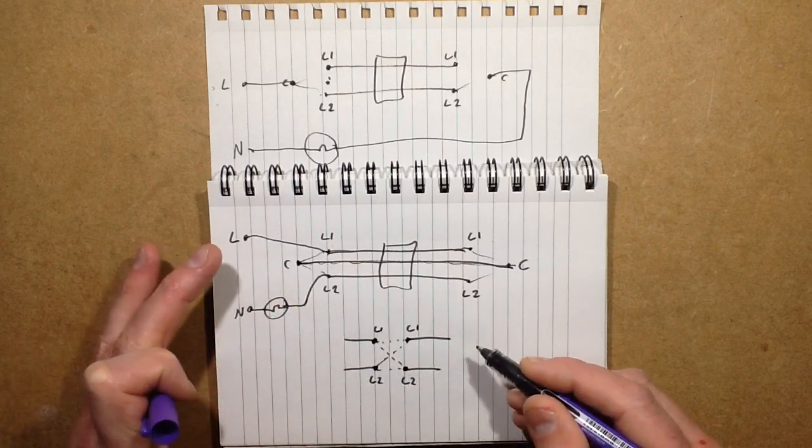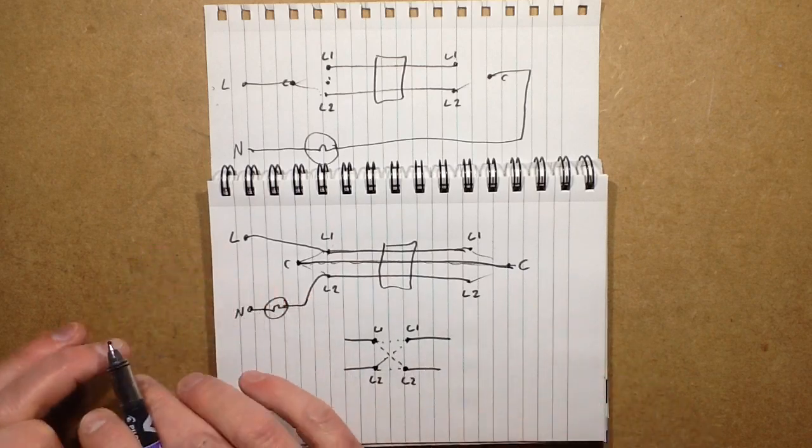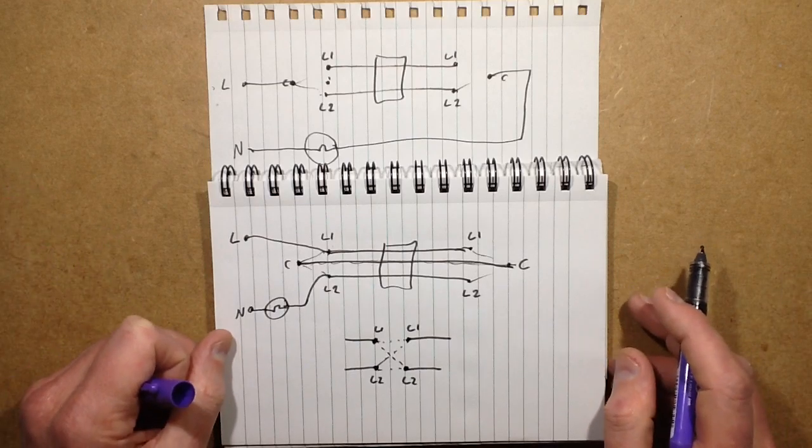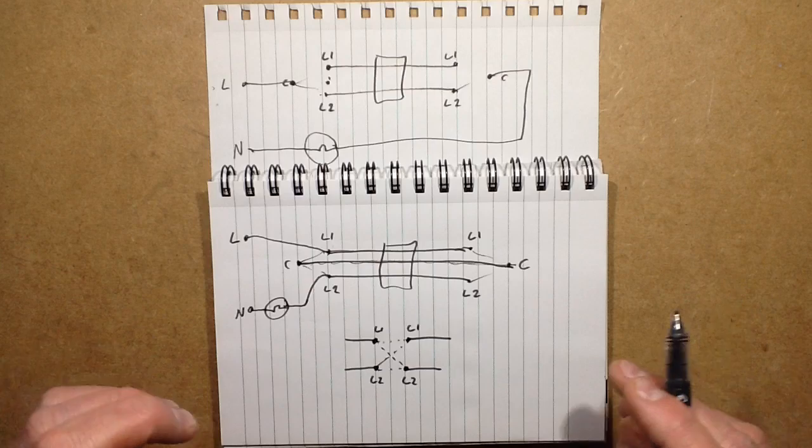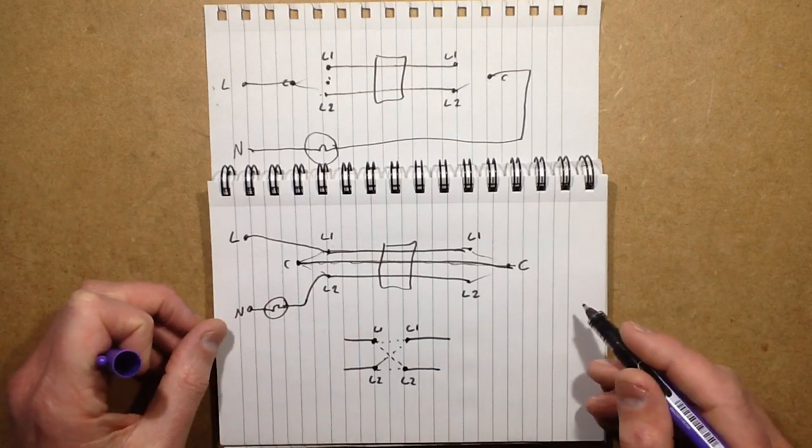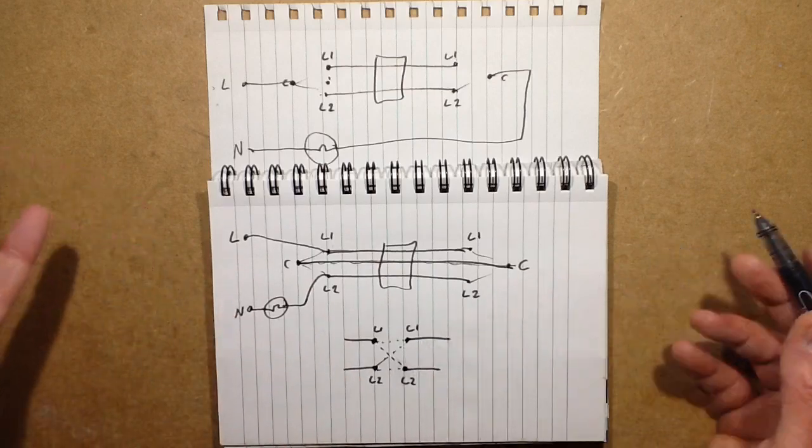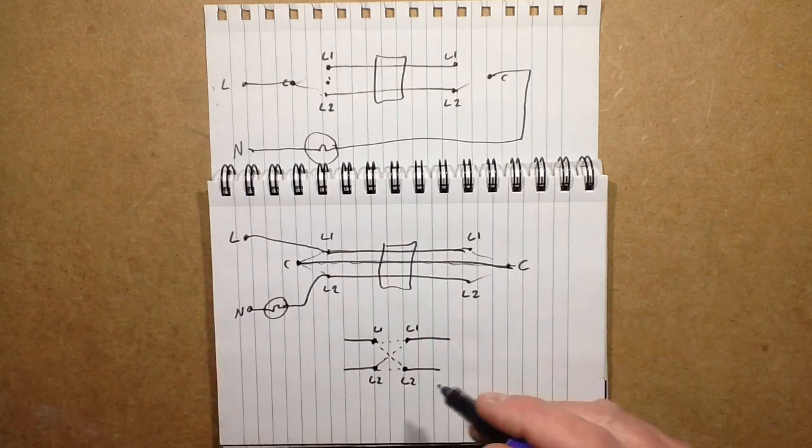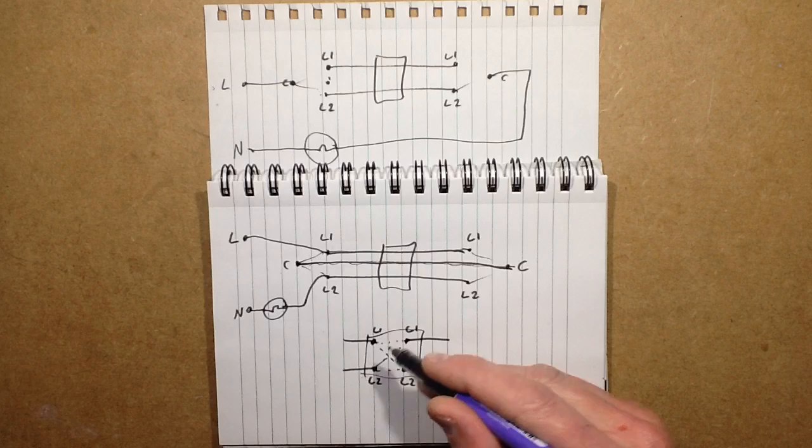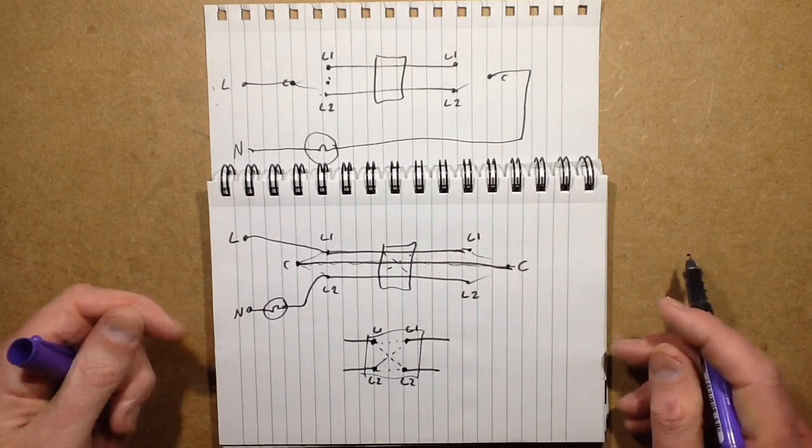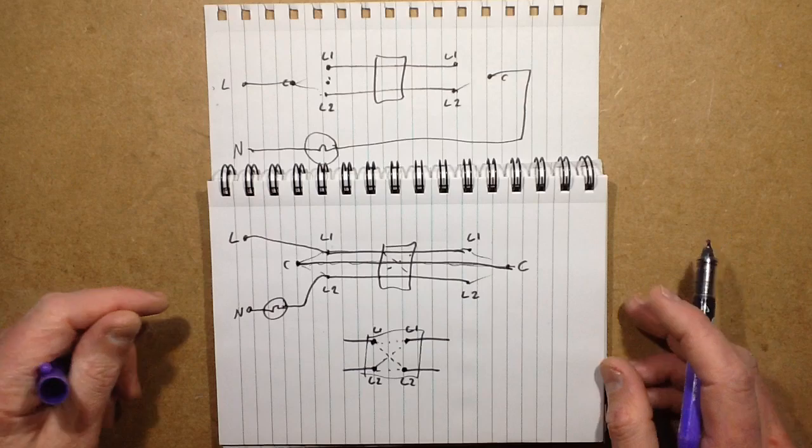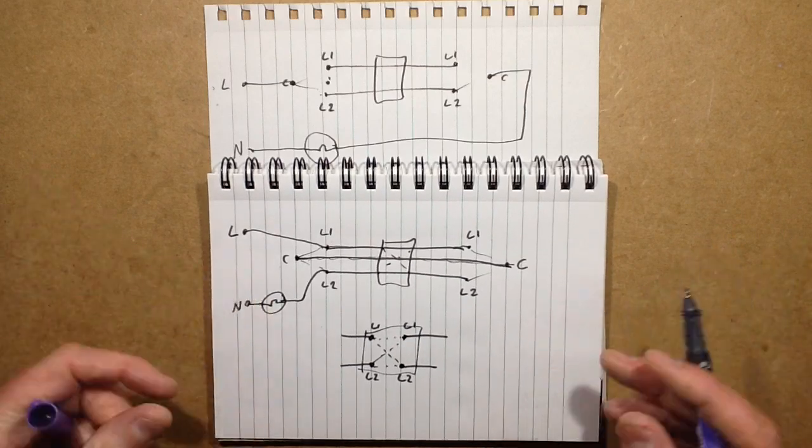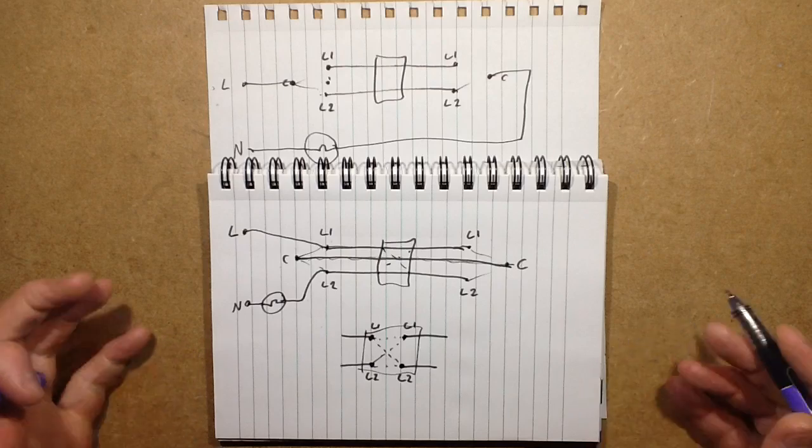And you can put as many of these switches anywhere along that line that you want. You could have a hotel lobby with 10 or 20 switches, 30 switches if you want, that switch the whole lighting circuit. Because basically just along those strappers you can just put extra switches in anywhere. So that's the principle of two, three, four, five, six-way light switching. Very, very simple. So worth playing about with and getting familiar with.